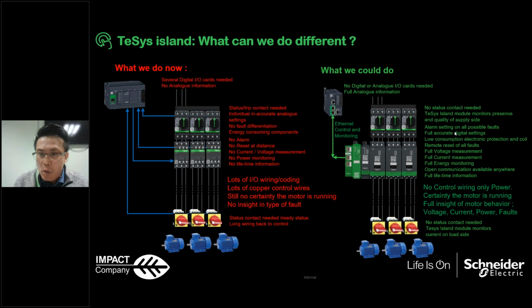We have alarms for all possible faults, so you can send different fault alarms to the operators before the failure. We have full, accurate digital settings. We have low-consumption electronic protections and coil. You can remotely reset all the faults. Of course, you have to enumerate the faults, but you can remotely reset all of them. We have full voltage measurements, full current measurements, full energy monitoring, and it is open to communicate everywhere. So this is what we can do more, to upgrade our system to a smart system.